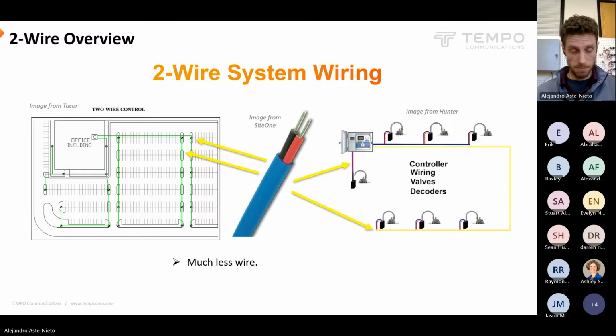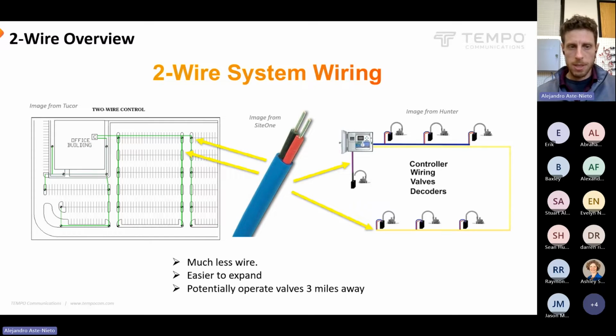And yeah, obviously the main benefit is less wire use, but these systems are also much easier to expand, because if you wanted to add a zone, let's say out here, rather than running a wire all the way from that zone to the controller and adding one more wire into your big bundle there, all you have to do is stick another 2 wires onto the end of this 2-wire path, and you've now linked it electronically. You obviously still have to put your water pipe there as well, but you don't have to dig up anything past the furthest valve to be able to expand. And these systems can operate valves from very far away. Some of them, valves three miles away, give or take. And again, dozens of valves along that same wire path out to that very, very far valve.